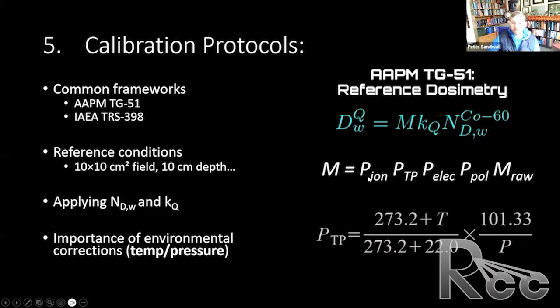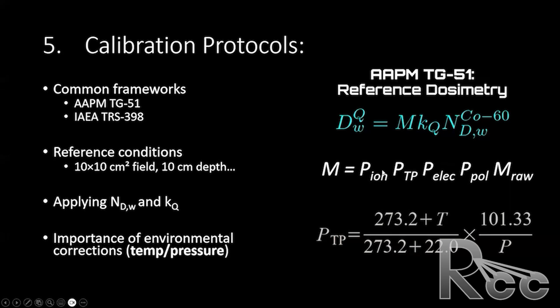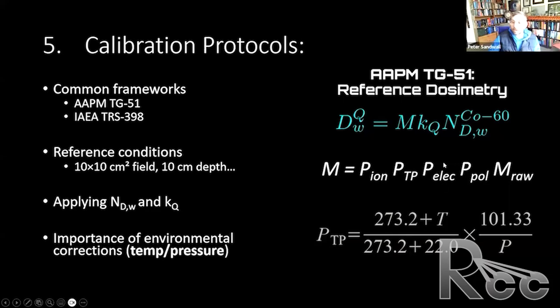Our corrected measurement is dependent upon the performance of the ion chamber itself. There's ionization, there's recombination, there's the temperature, pressure, there's the electrometer, there's the polarity, and then obviously we use the raw reading corrected to get this value. So there's a whole chain, and I think the temperature and pressure is one of the most important to be sensitive to, and we'll talk about that, is that some people might not have access to calibrated thermometers or barometers, and this is something that really is important. It's essential. This has actually led to a lot of errors, using the wrong barometer or using the wrong thermometer, and we'll talk about that. We'll mention some specific cases in which this has occurred.